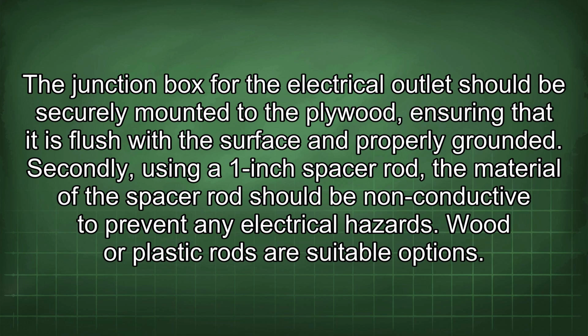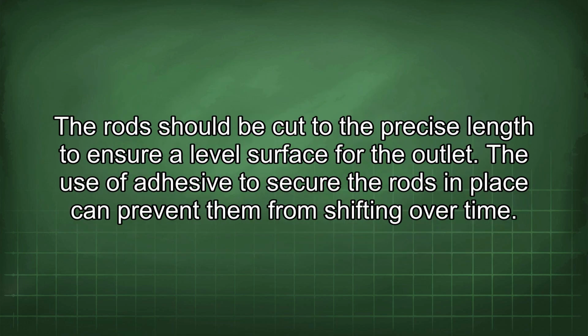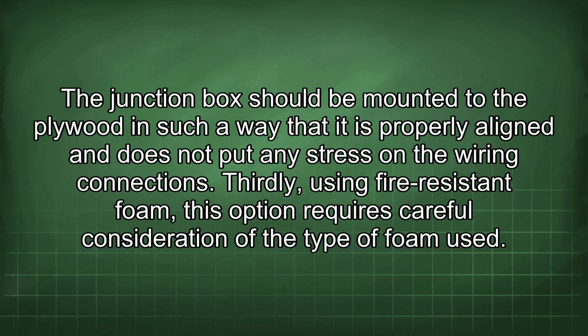Secondly, using a 1-inch spacer rod. The material of the spacer rod should be non-conductive to prevent any electrical hazards. Wood or plastic rods are suitable options. The rod should be cut to the precise length to ensure a level surface for the outlet. The use of adhesive to secure the rods in place can prevent them from shifting over time. The junction box should be mounted to the plywood in such a way that it is properly aligned and does not put any stress on the wiring connections.